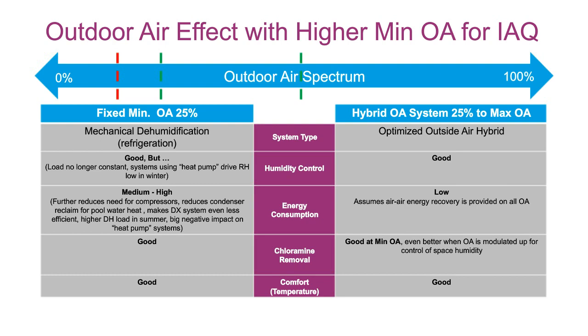So it really isn't a very good system when you don't need to run your compressors. The job of chloramine removal now, because we're getting more fresh air to the space, and the comfort would still be fine. The outside air, if we talk about the hybrid system, really then we're going to modulate from 25% to whatever the max outside air setting is, 40 to 60%. Typically, your humidity control is good. Your energy consumption is quite low, and you're doing energy recovery. When done correctly, you're going to be doing energy recovery on all of the fresh air you're bringing in, so you can keep the increased outside air impact down. Your chloramine removal is great. It's set for minimum outside air, and then when you do modulate up for that efficient dehumidification, you do even better, and the comfort, again, is good. So it really doesn't have a major effect on the outdoor air system because it was designed for it.